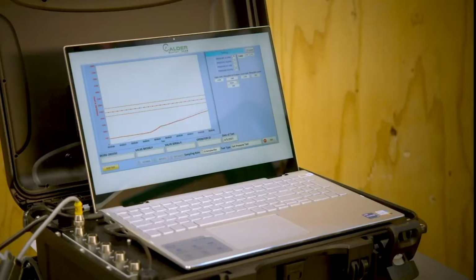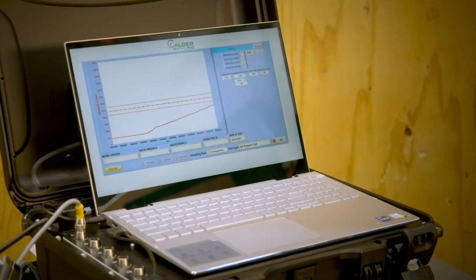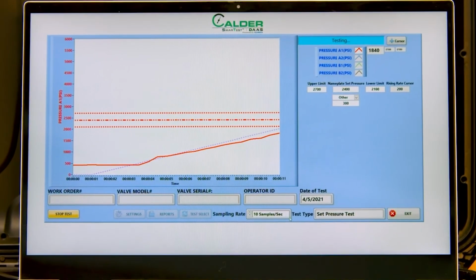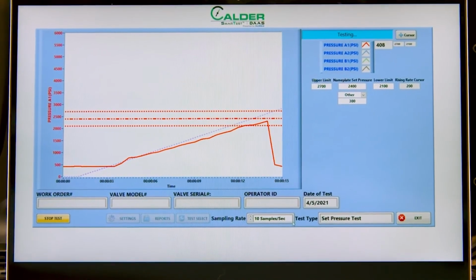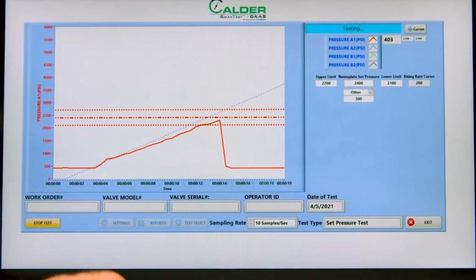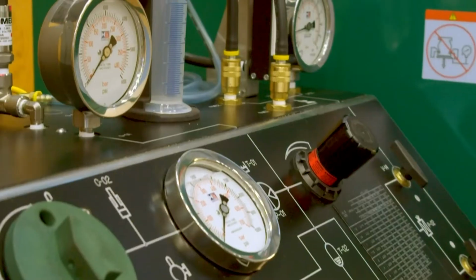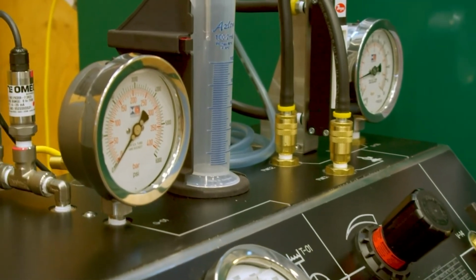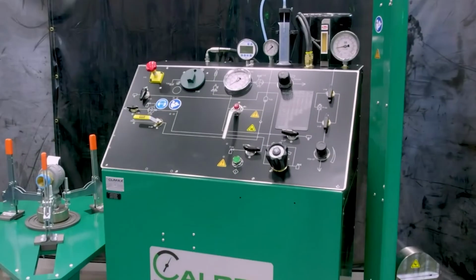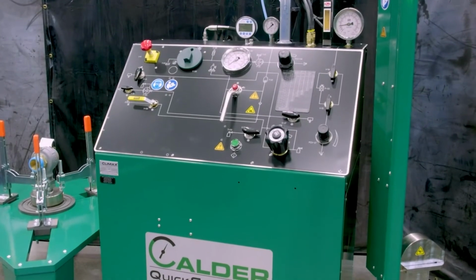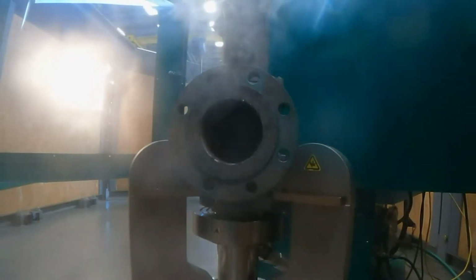Smart Test intelligent data acquisition system digitally indicates while recording tests for both seat leakage and set pressure, providing auto pass/fail with the software and integrated laser bubble counter according to most major standards, including API 527. The QUICKSET has the ability to do both gas as well as gas over water, allowing the owner-operator to test both gas as well as liquid safety relief valve.